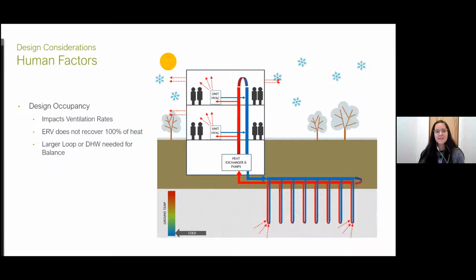Our mechanical designers were less familiar with it, used to designing for one worst case happening on top of another, on top of another, which wasn't necessarily realistic or something that would happen often enough to warrant designing the system at such a large scale. So we had a lot of discussion about peak design with a high factor of safety versus a leaner approach targeting what's actually needed.